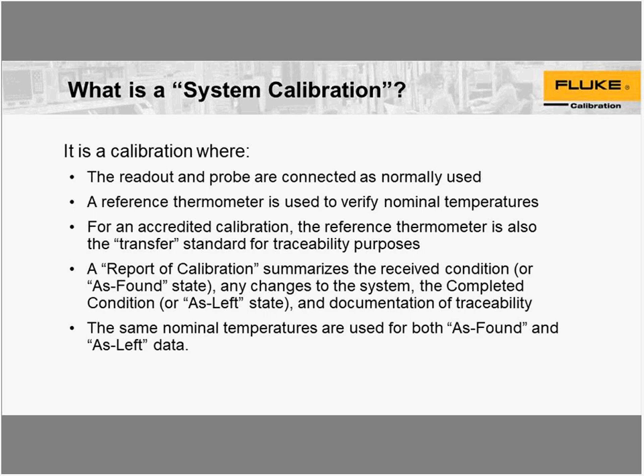For accredited calibration, the thermometer is also used as a transfer standard, and that will aid in your traceability purpose. A report of calibration summarizes the received condition or as found state and any changes to the system that are made, a completed condition or as left state, and then also documentation of traceability. The nominal temperatures are used for both as found and as left data.